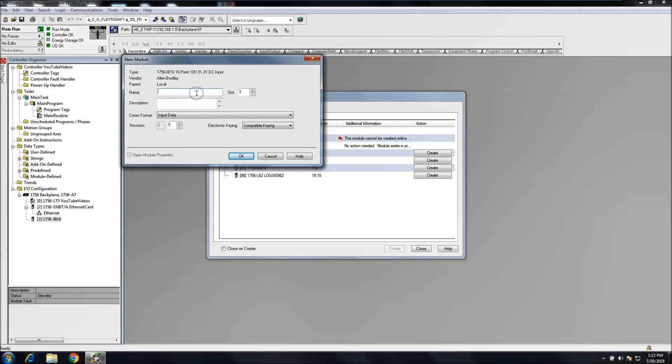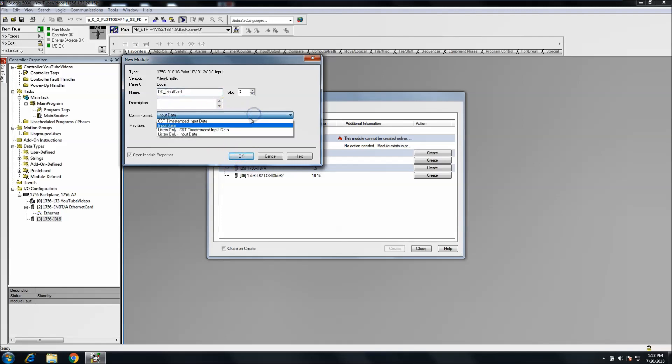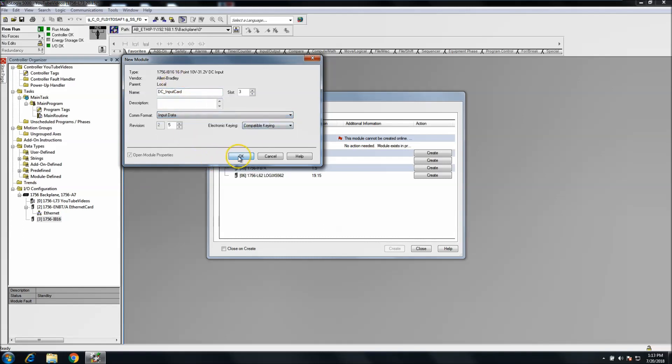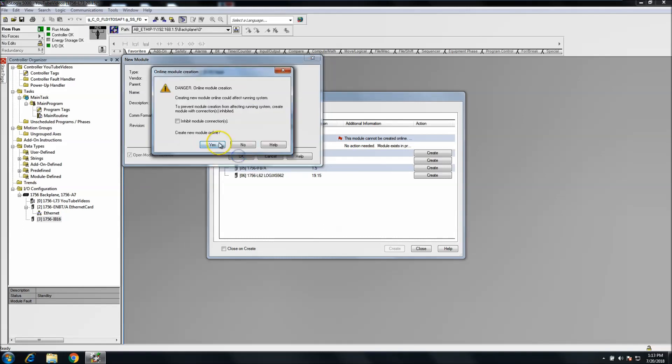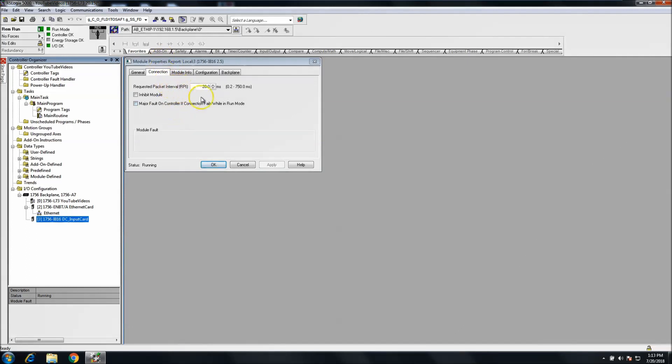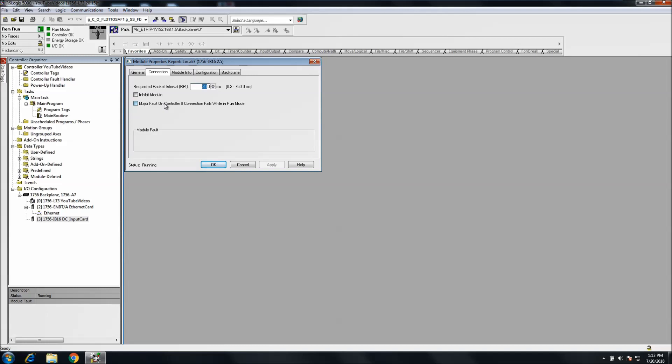Now we're going to do our input card, this is our DC input card. You can select the formats that you want depending on what card and firmware you have. In this case, we're just going to go with generic. You can put your RPIs, your requested packet intervals, basically your timing of your IO talking between the backplane. If you have real fast IO, you can shrink it down anywhere between 0.2 to 750, or basically three quarters of a second.